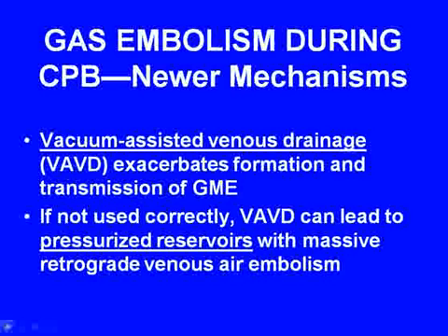A potentially lethal mechanism when using VAVD occurs when the hard shell reservoir has vacuum applied either before starting bypass or after bypass has been stopped. And this can lead to air being drawn into the arterial side of the circuit through the membrane oxygenator or arterial filter.